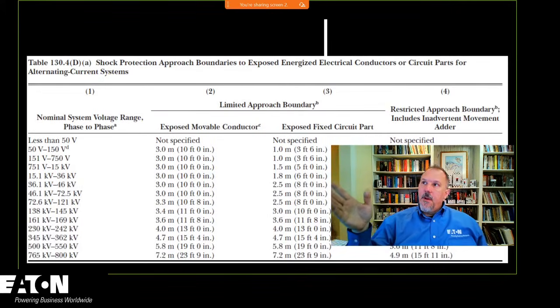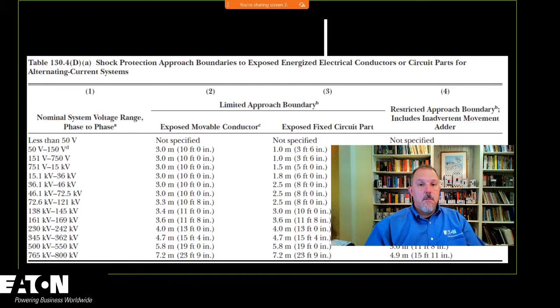And I had a slide in here. I put the table 130.4DA, which talks about the AC side. And so 50 volts across the board, AC and DC, that's the established threshold from a shock perspective, right? Yeah, and this is the AC table here. Right. But this is limited approach boundary. We're really not using the exposed movable conductor. You can see that superscript C, and it'll tell you that that's associated with conductors on poles. So we're always in 3 for the limited approach boundary and 4 for the restricted approach boundary.